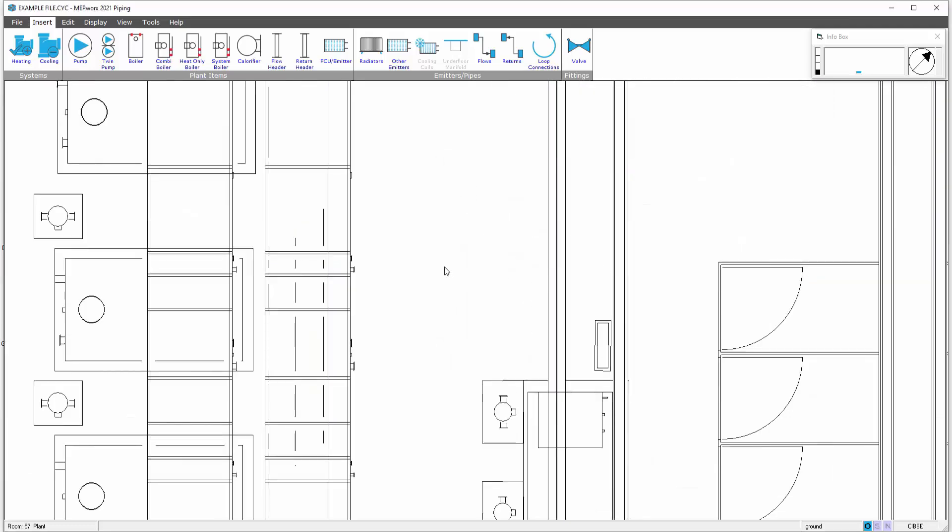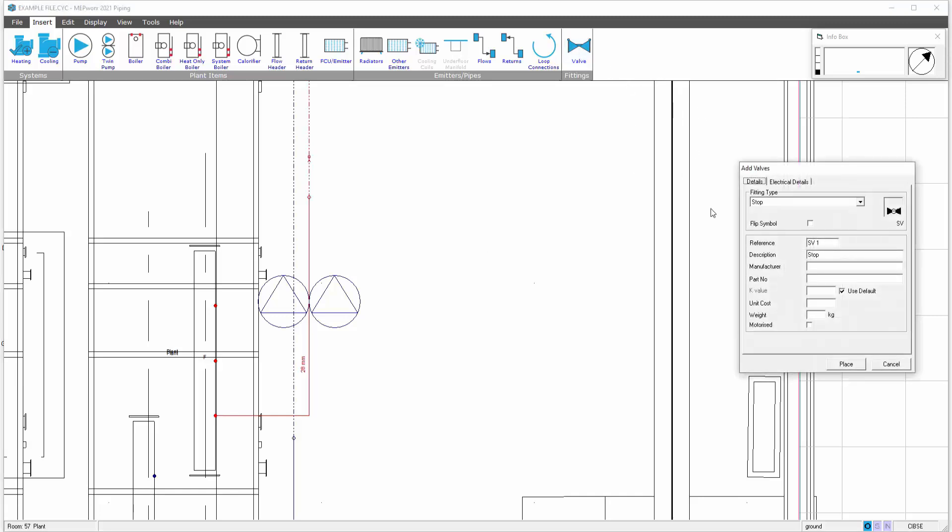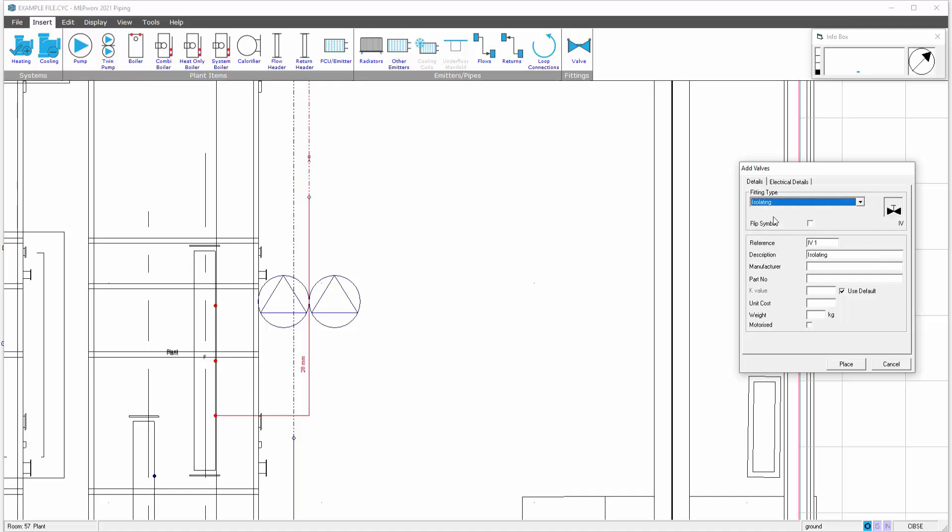Adding valves is a very similar process. You can either add manual or motorized valves. Selecting the valves option, selecting the valve that you want. You can use default K value or you can enter your own K value along with many other parameters. You can see here you've got a motorized option. Should it be motorized, enter the tick box and that will then invoke the electrical tab so the load can be applied.